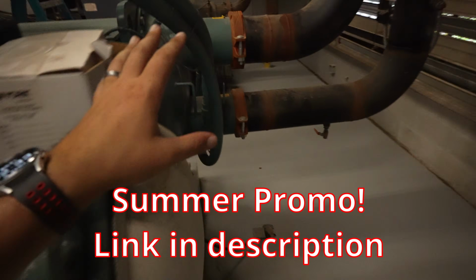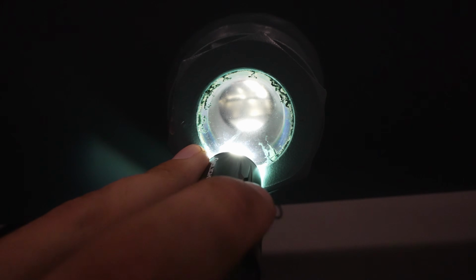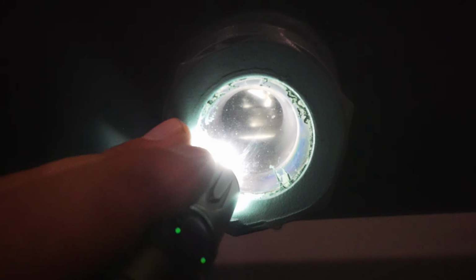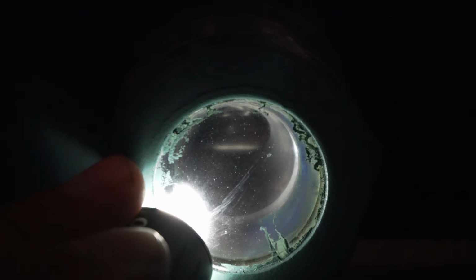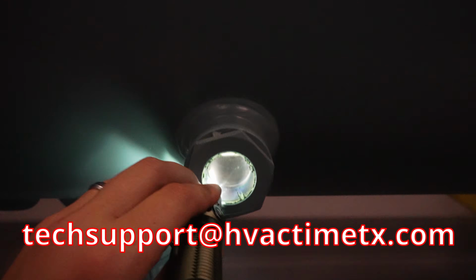So I do my normal inspection checks. I'm walking around, walking around. This is typically what I do. I come over here to my liquid level sight glass and I shine in there, and my liquid level was right here, at the bottom of the glass. When you can see the top of the subcooler in there, that's that big shiny plate in the bottom. The top of the subcooler was actually above the liquid level. Well, that's a really big issue.